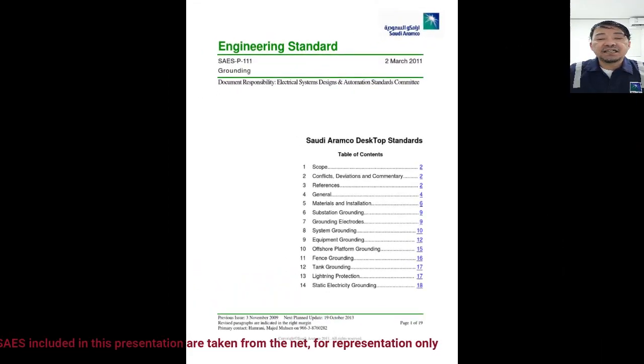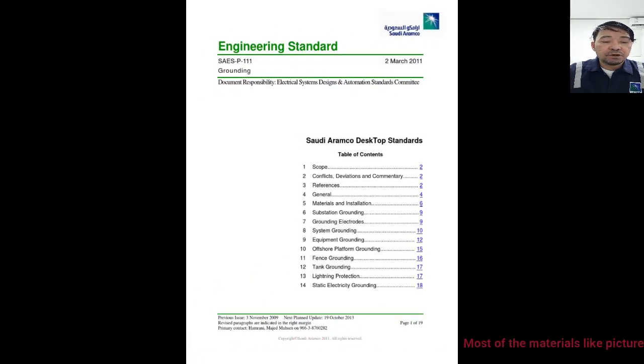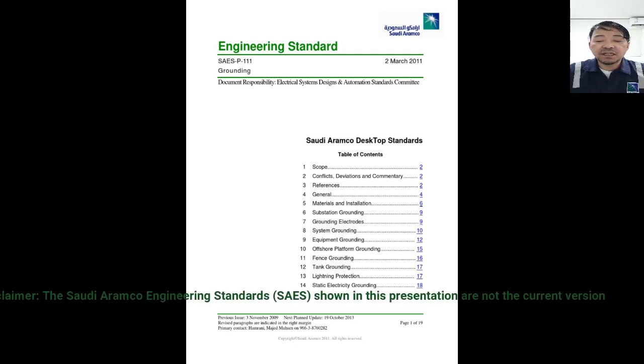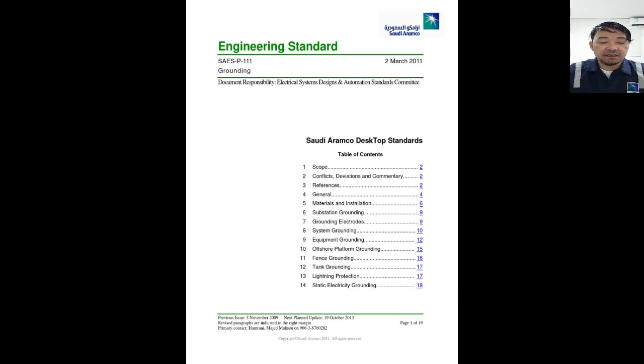We have testing criteria. For individual rod test, resistance shall not be more than 25 ohms for single rod testing. If not, additional rods will be added. As per SAES-P-111, paragraph 8.2, solidly grounded system below 1 kV, and SAES-P-111, paragraph 8.2.1, the ground resistance of made electrode ground rods or grounding grid used for system grounding shall not exceed 5 ohms.